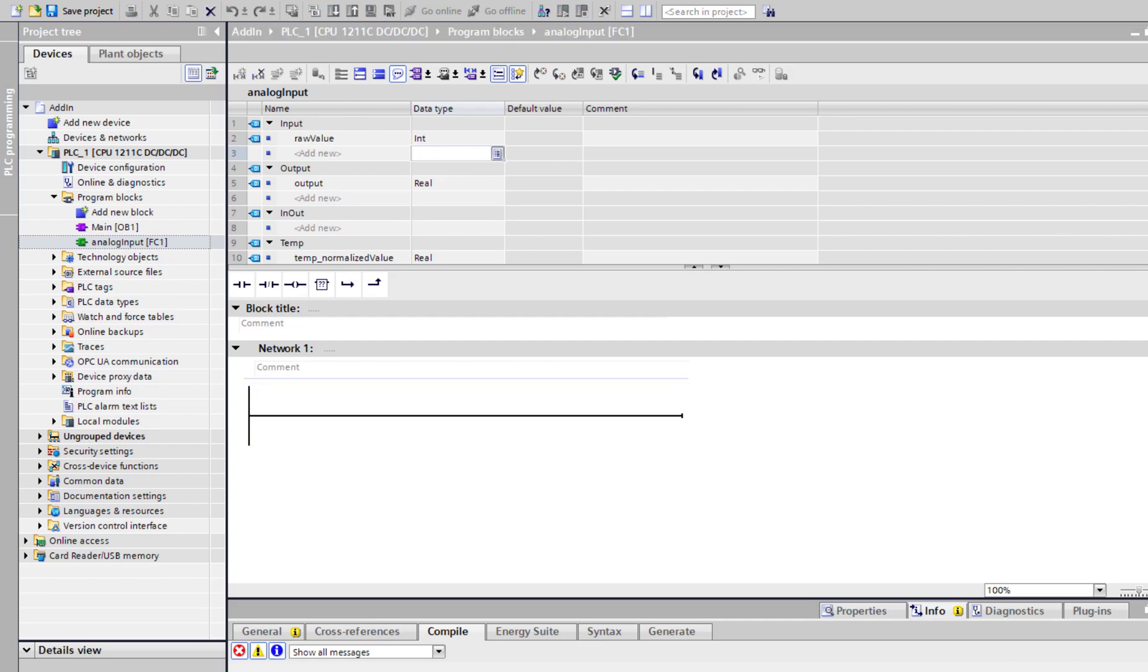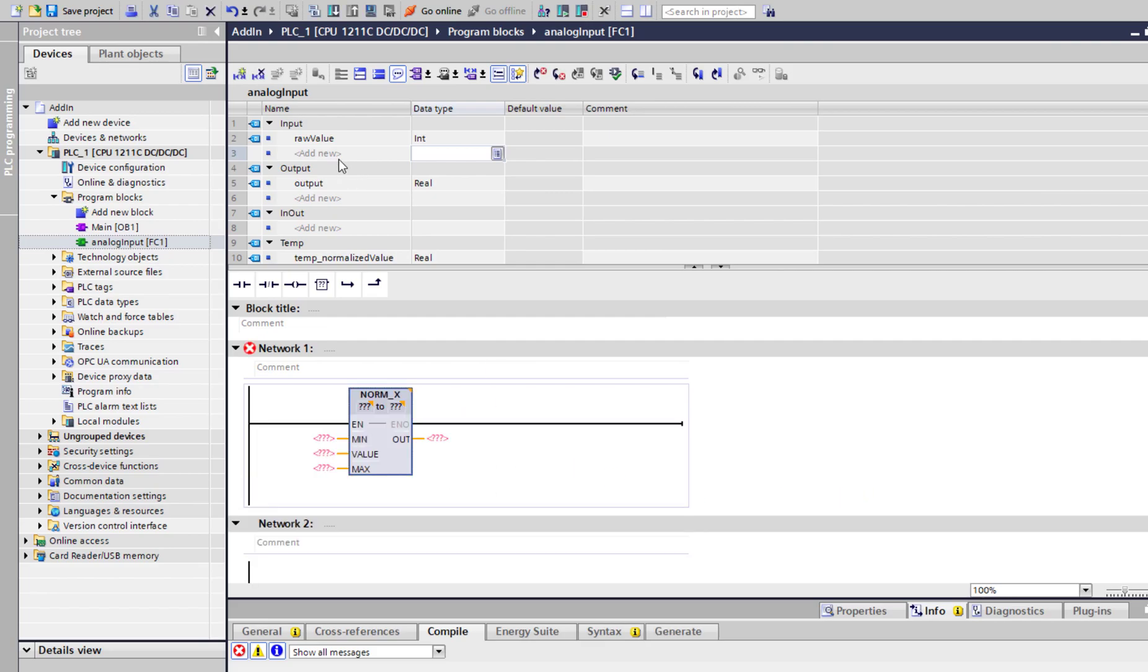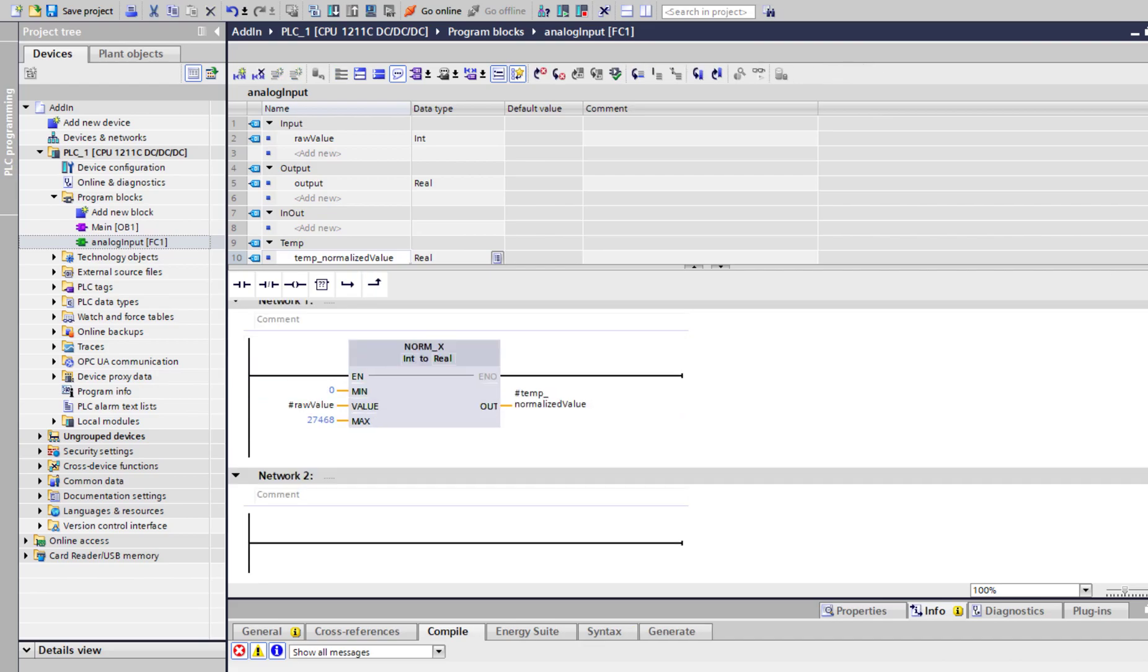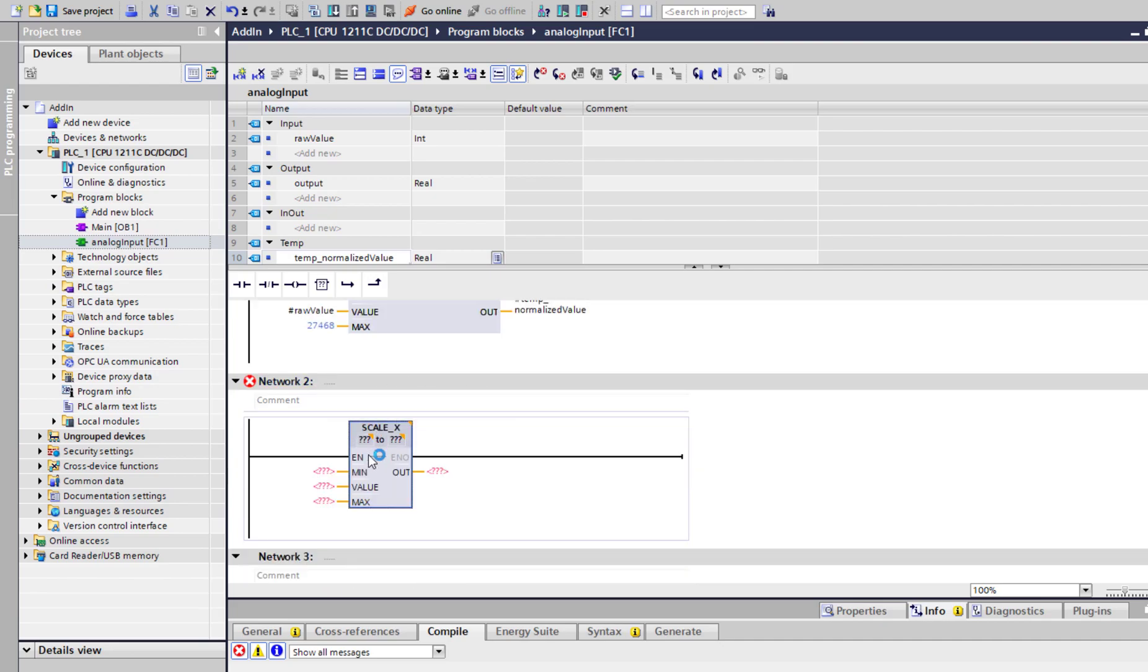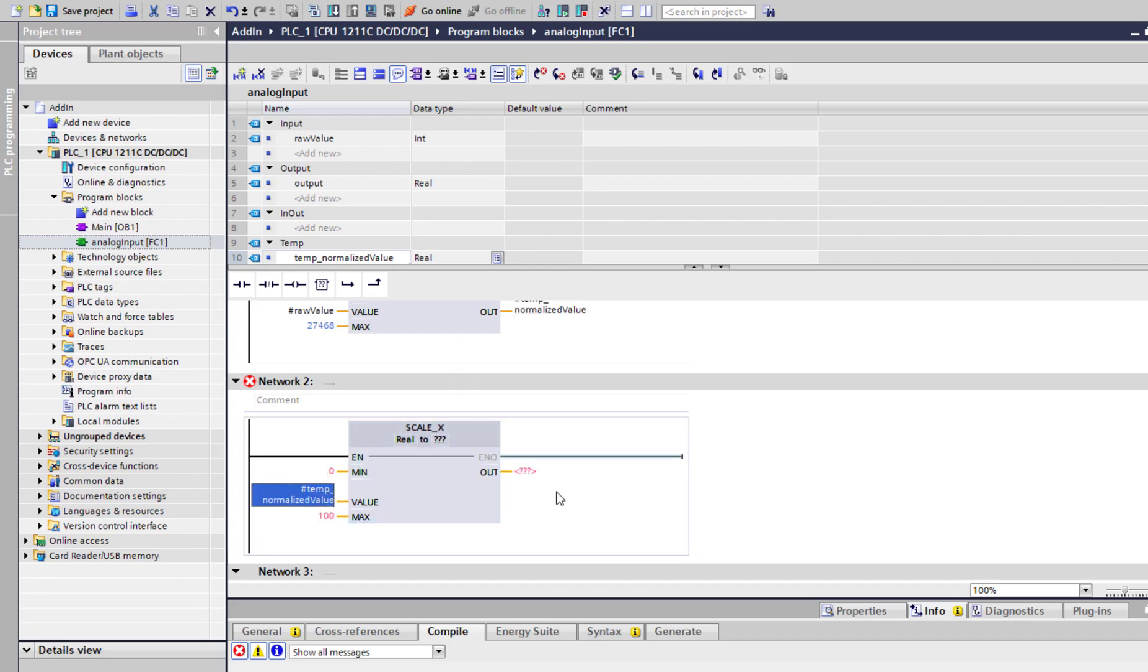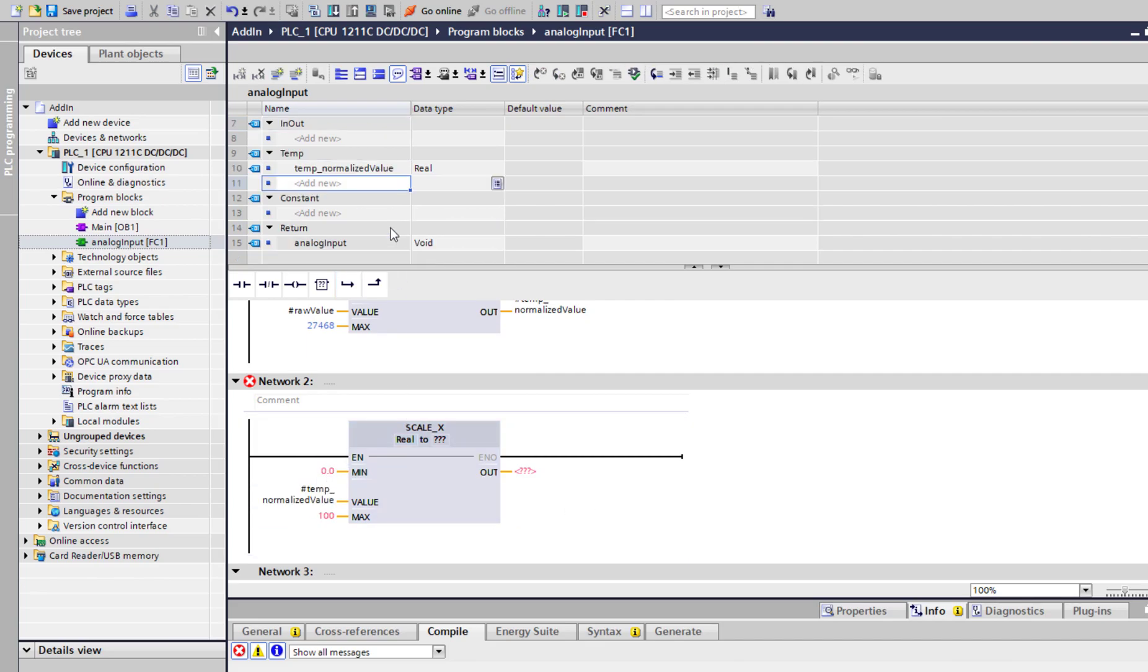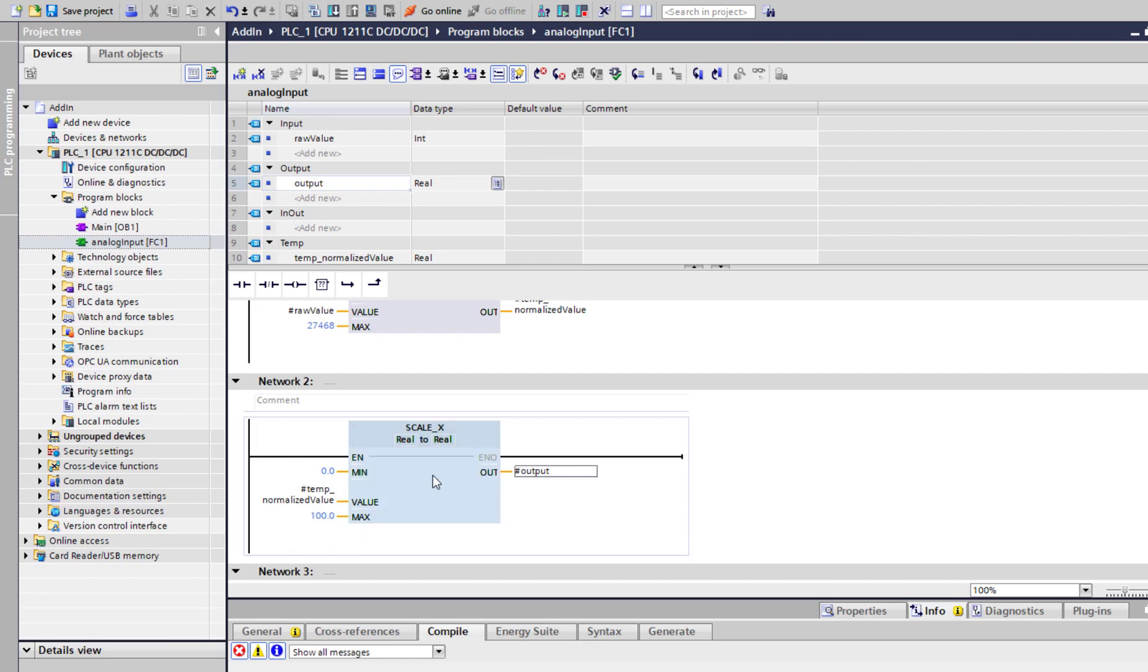Let's say NORM_X. I grab this. 0 to 27647. Output is normalized value. Then I will scale it. If you don't know where this is coming from, please do check out my other video. We'll do 0 to 100. This and then we have, where is our output? Our output. All good now.